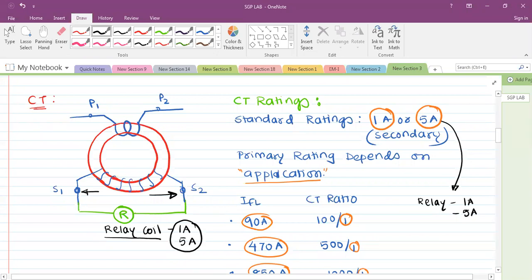either having a 1 ampere rating or 5 ampere rating. What if we do not standardize the CT rating? Then it will be very difficult for relay manufacturers to specify the design of a relay. Moreover, these standards are generally very useful in technology exchange.